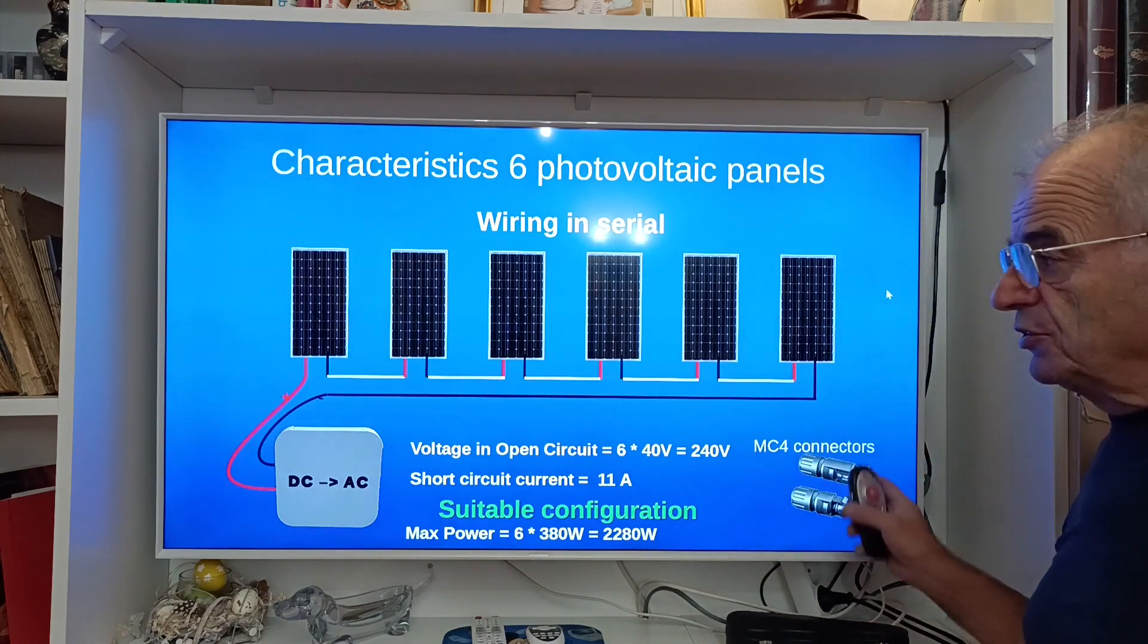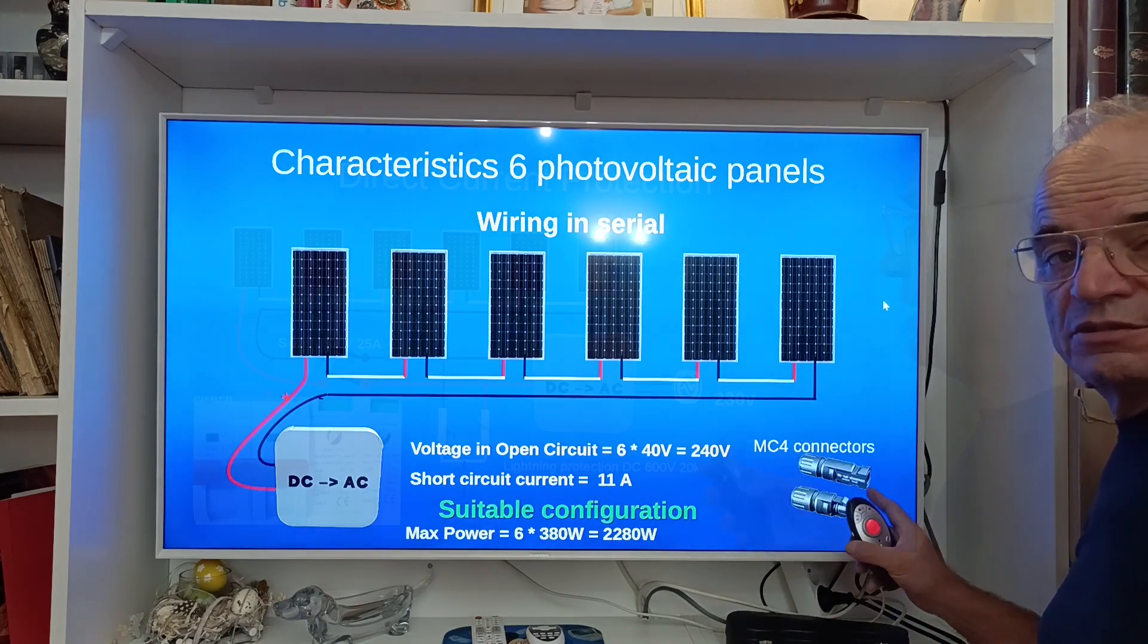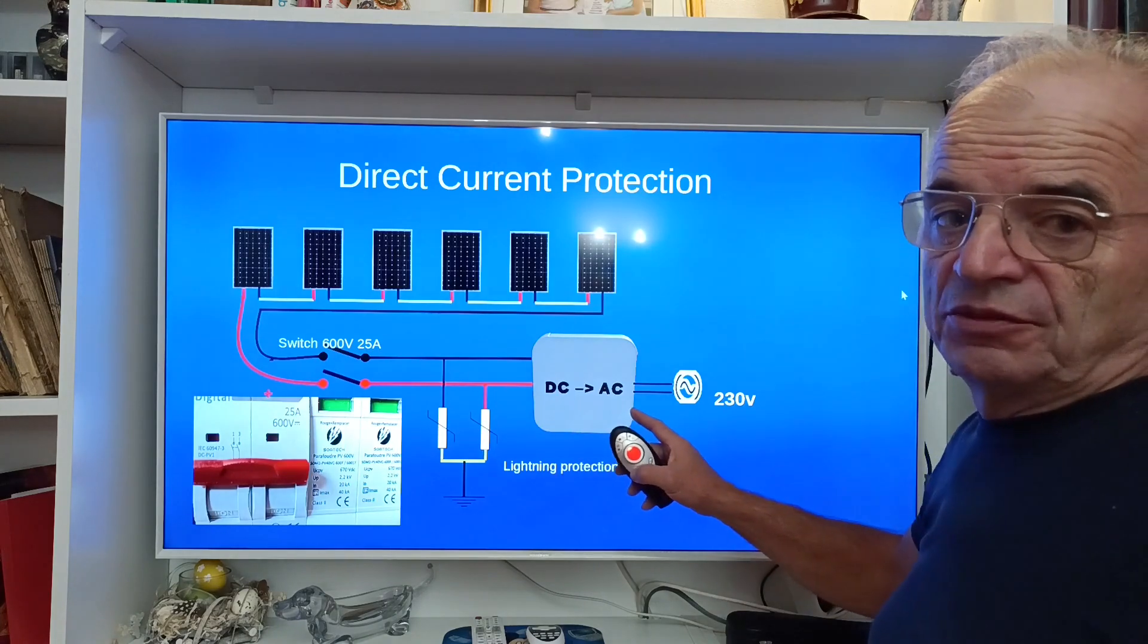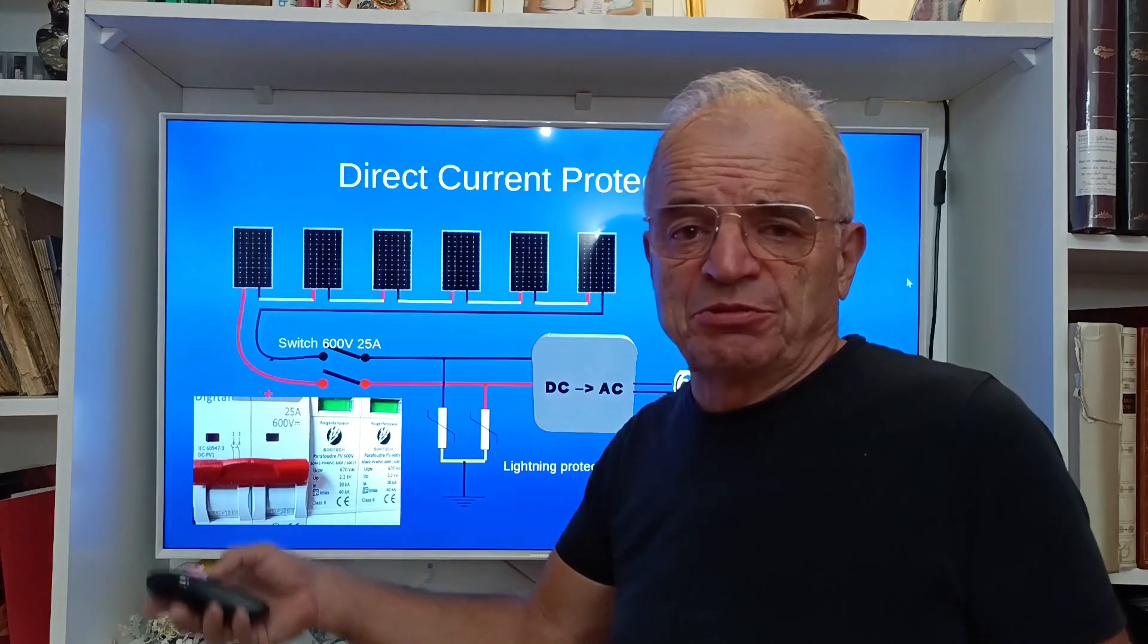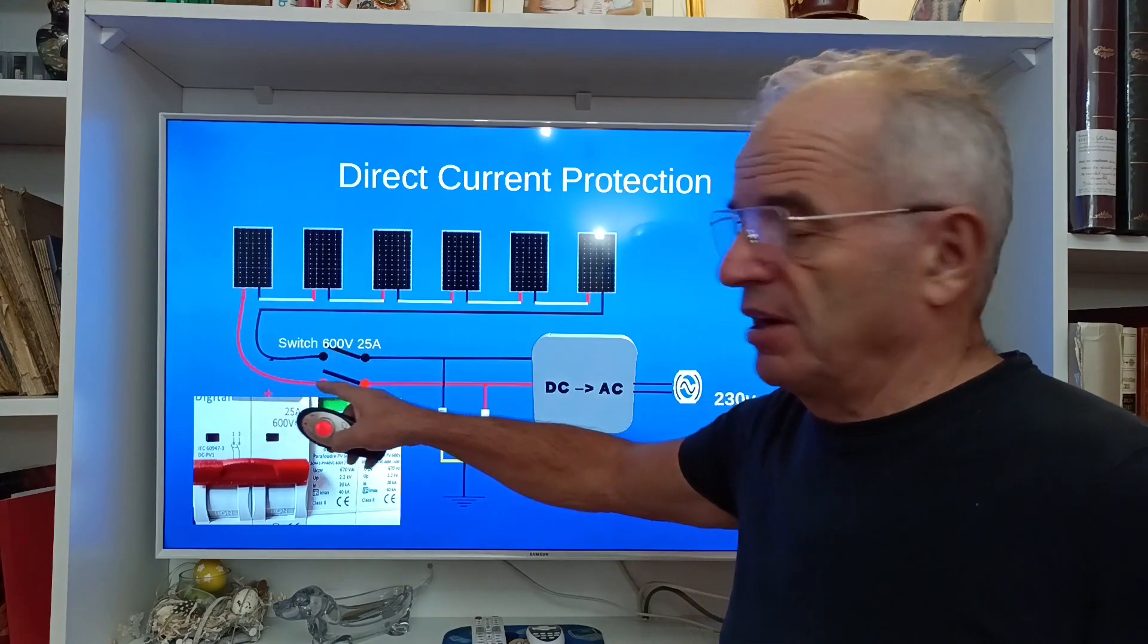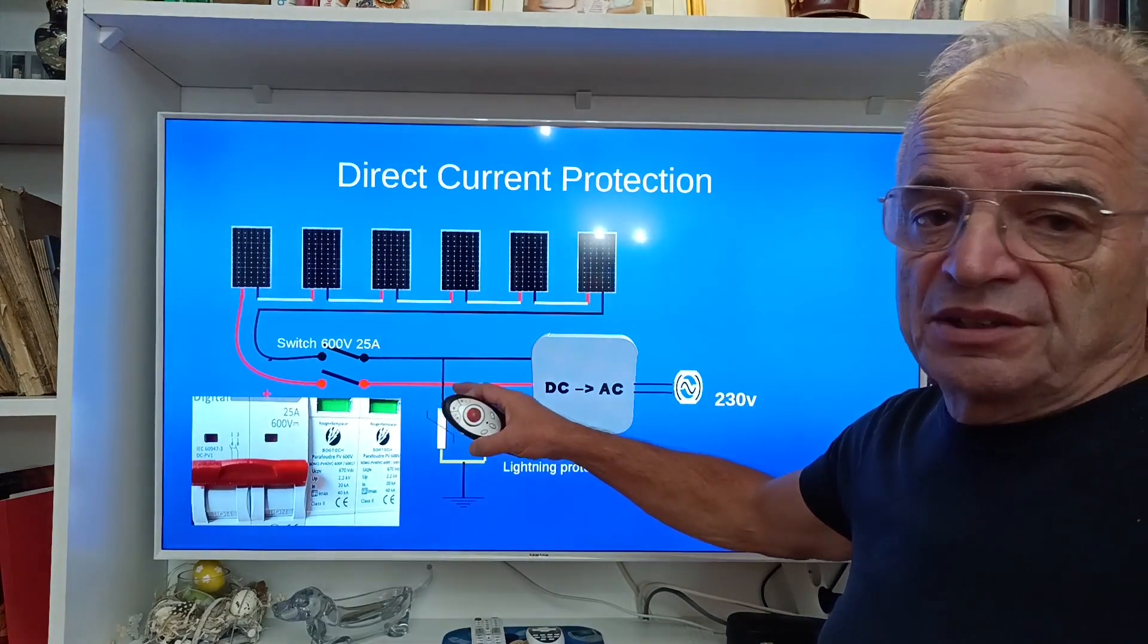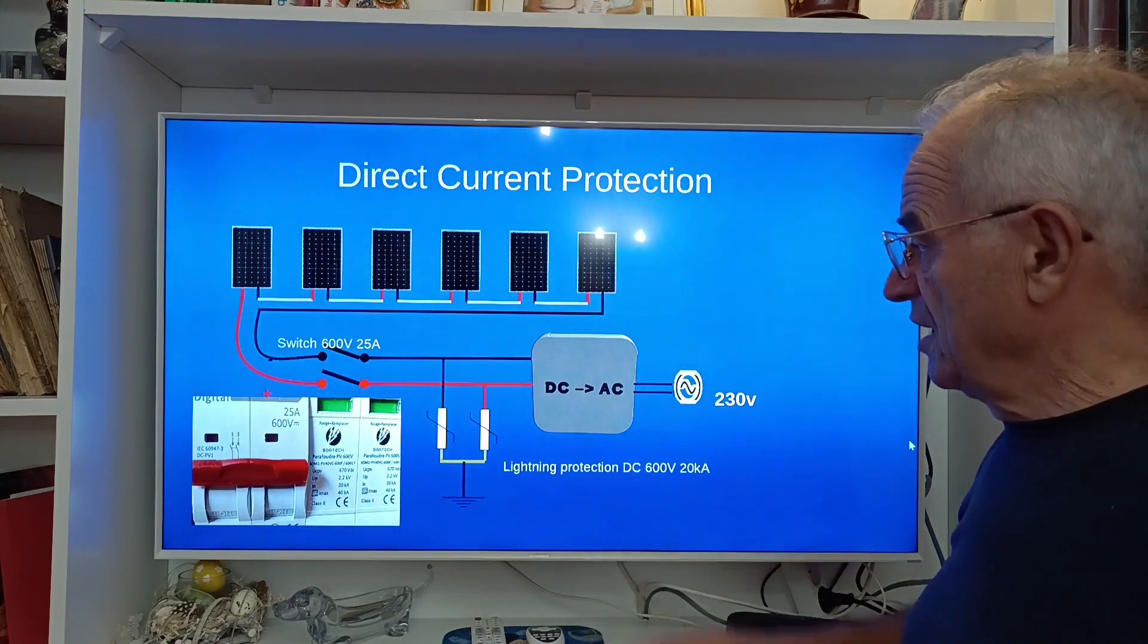Most of the time those panels are connected using what we call MC4 connectors. When we have these six panels before connecting them to the DC to AC converter or the inverter, we need to put a switch. You can understand simply for security reasons, we have to be able to switch off the access to the DC part during the installation. So we have a switch here, but the standard also requires that we put this lightning protection dedicated to DC current.